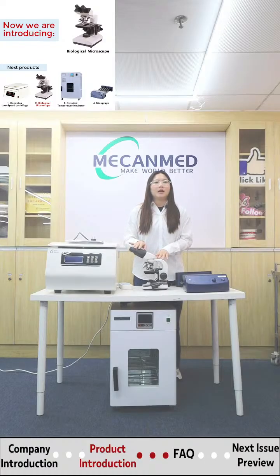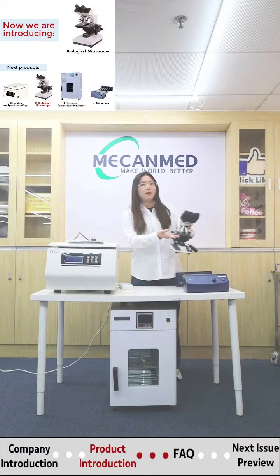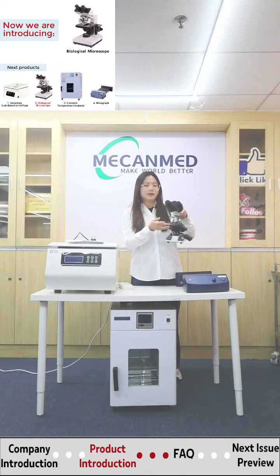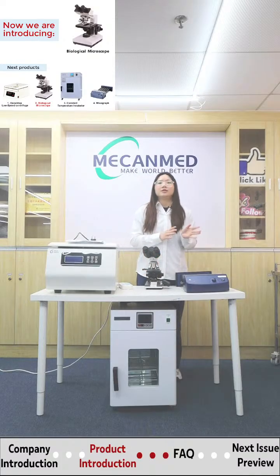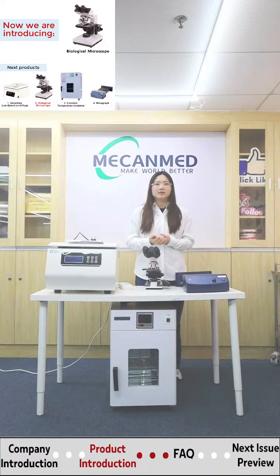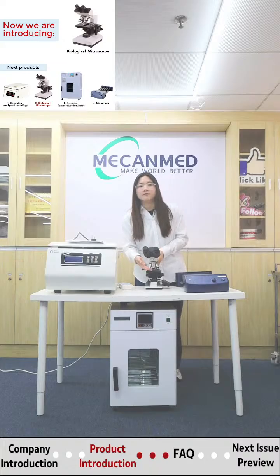And our products will give you a smooth, professional experience every time you use it. It is primarily composed of mechanical, illumination and optical modules. The mechanical module primarily consists of the base, arm, tube, nosepiece, stage, and the coarse and fine focus knobs. The illumination module includes the light source, condenser, and diaphragm, and the optical module is mainly composed of the eyepieces and the objectives.